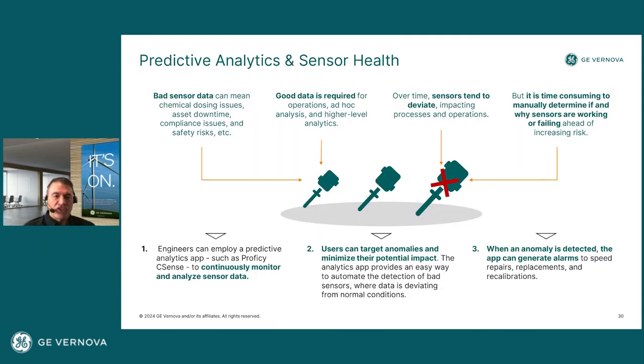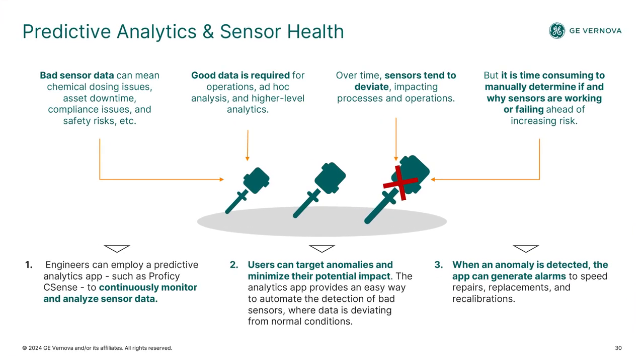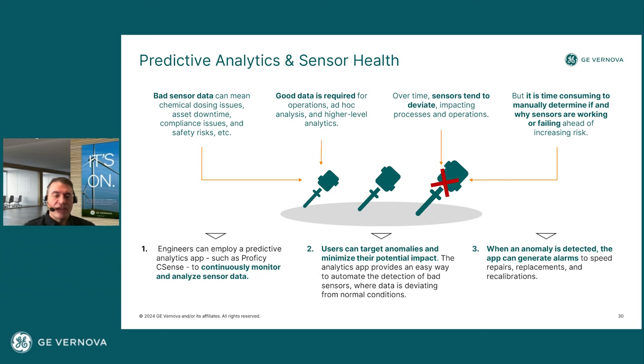I also mentioned sensor health. The idea is to monitor that data, because ultimately if the data is bad, you're probably not controlling your process correctly either—if the data you're relying on isn't reliable. So the idea is to detect those anomalies, things like flatlining, out-of-range values, or data deviating from the norm more than usual. These tools give you an early warning. It may or may not be an issue, but if an anomaly is detected, you can investigate—maybe it's a bad sensor that needs replacing or cleaning.